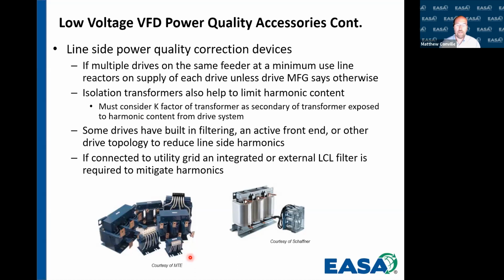Some drives already have built-in filtering in their active front end, or they use other drive topologies with multiple pulses to actually reduce line side harmonics. If we're connected directly to a utility grid, we either have to have an integrated or an external LCL, which is an inductor, capacitor, and inductor filter, and that's required to mitigate harmonics. So here's just a couple examples of some inductors and an example of an LCL filter.